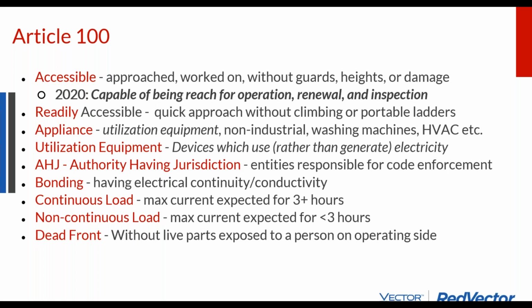Continuous loads and non-continuous loads. The magic number is 3 hours. So if a load is expected to run for 3 hours or more, it's a continuous load. Loads that are non-continuous run for less. More on that later.